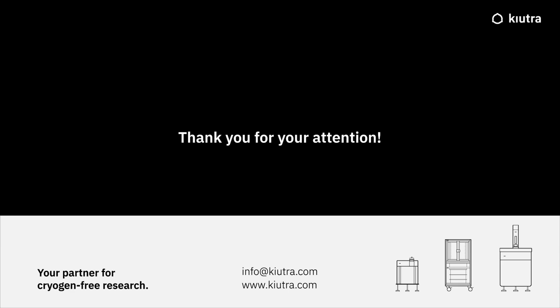Understood. Is there a wire breakout box for all the available connections on the sample puck? Yes. So the system comes with a breakout box that offers connection for each individual pin or bondable terminal on the puck. We also offer other breakout boxes, for instance, those that are built by QDevil, which are optimized for measurements of very sensitive quantum systems. So we can also install these directly at our factory.